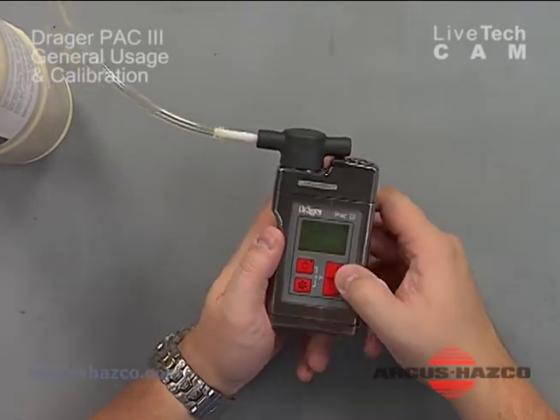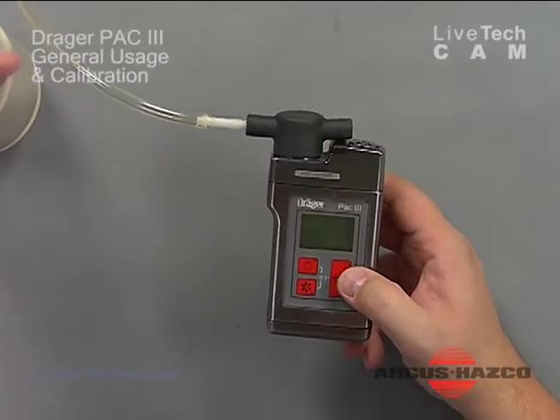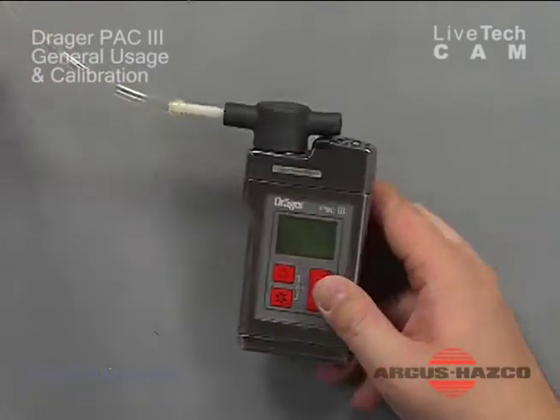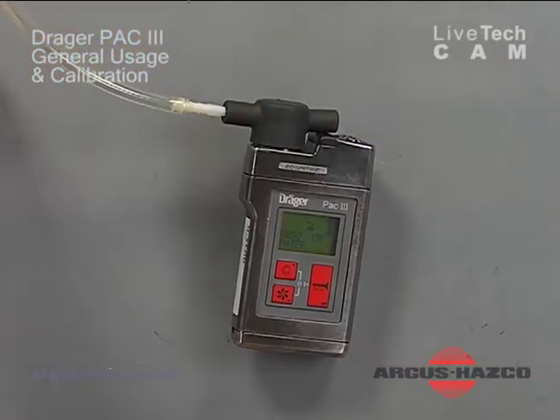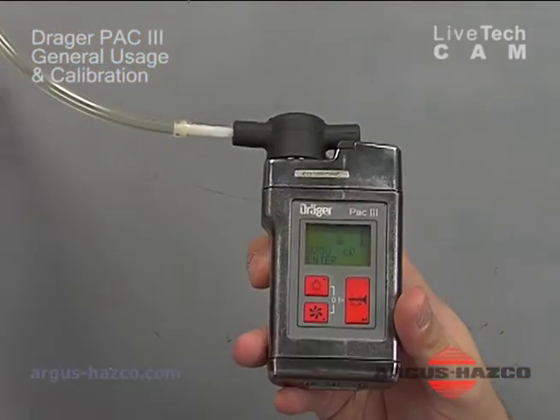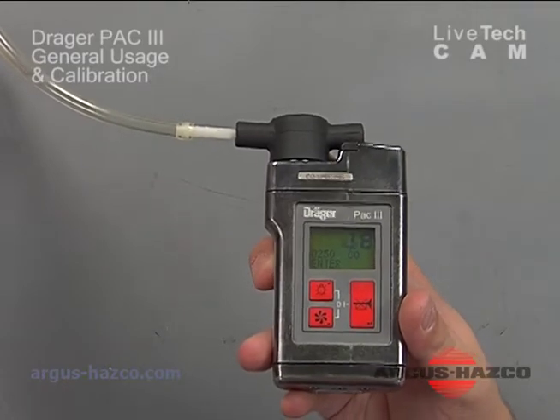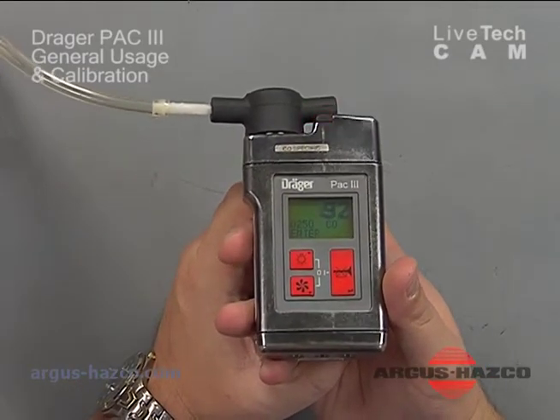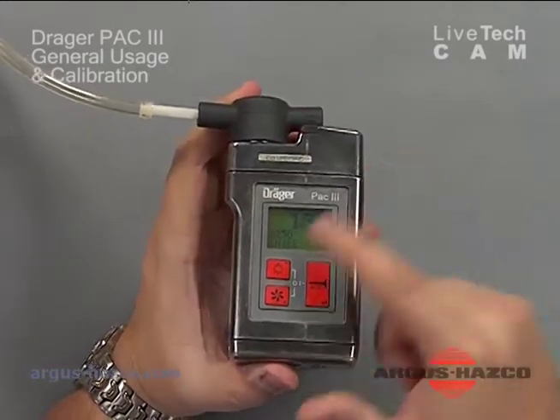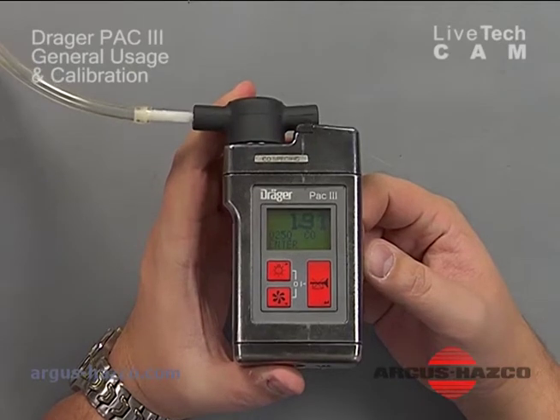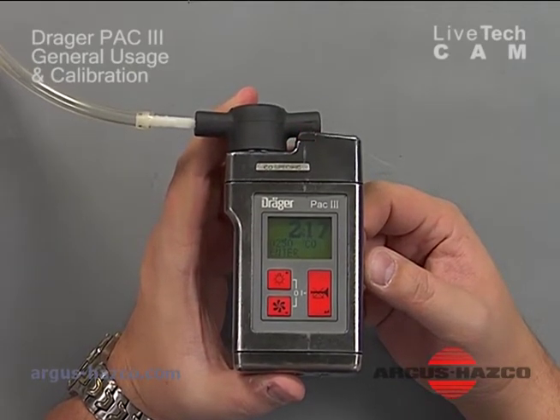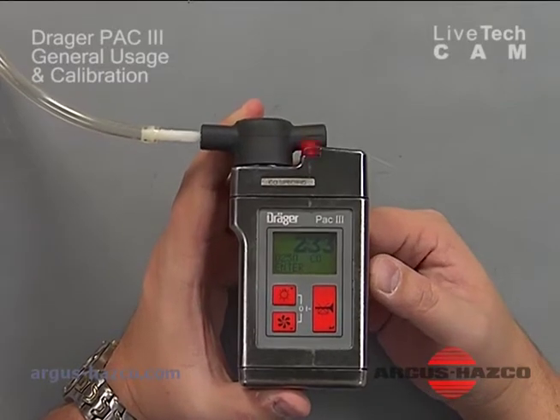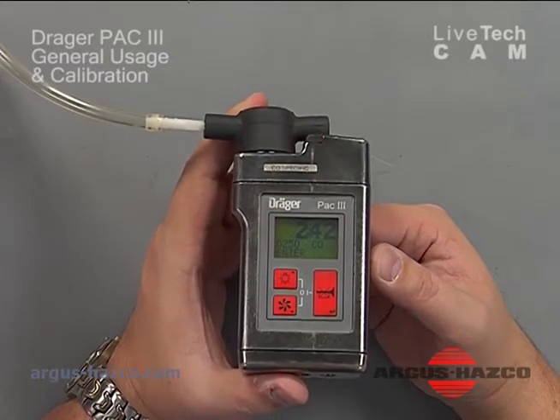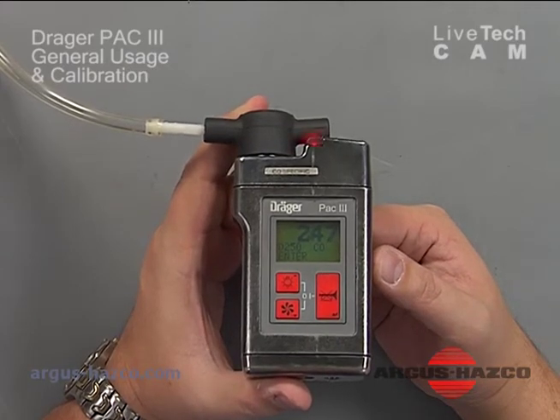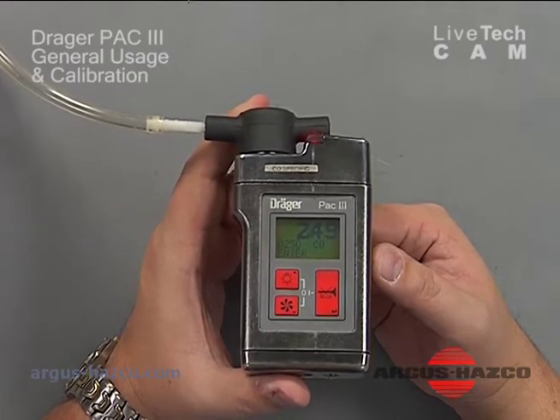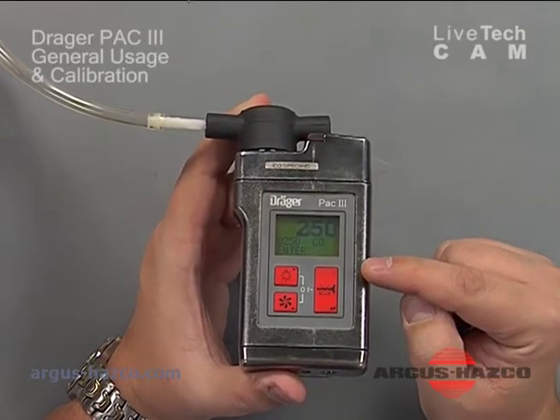At this point, you can hit this. You can enter the span and turn on your calibration gas. And you'll start to see the reading start to rise. You want to wait for this reading to stabilize before you hit your enter button, as it's indicating here, because you want to make sure that's stabilized, and then it'll make an adjustment after you hit enter. If it's still stabilizing, you can really be off on your calibration. We're looking for 250 parts per million. You see it's basically stabilizing now. It's at 247, 248, 249, 250.